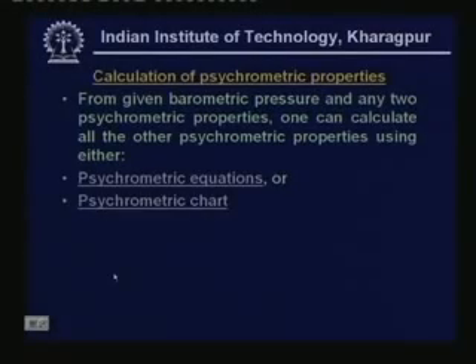Now the same thing can be done very easily using the psychrometric chart. For example, in the psychrometric chart, I have already shown this chart in the last lecture, and I have explained to you what are the different lines. Suppose we know dry bulb temperature and let us say relative humidity. So for example, it is given that this is the dry bulb temperature and this is the relative humidity. These two are given, and obviously the barometric pressure is also given. So one very important thing while using psychrometric chart is to make sure that you are using the right chart. That means you must use the chart given for that particular barometric pressure.